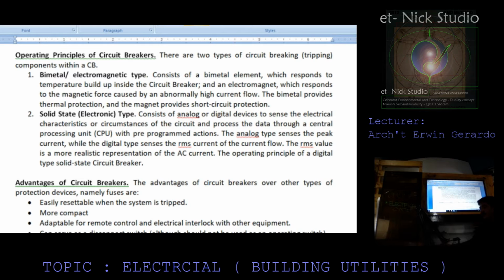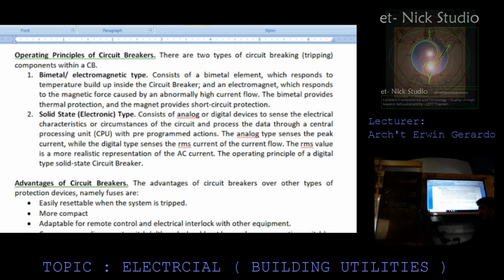Number two is the solid state electronic type. It consists of analog or digital devices to sense the electrical characteristics or circumstances of the circuit and process the data through a central processing unit or CPU. With a predetermined program's actions, the analog type senses the peak current, while the digital type senses the RMS current of the current flow. The RMS value is a more realistic representation of the AC current. The operating principle of a digital type solid state circuit breaker.